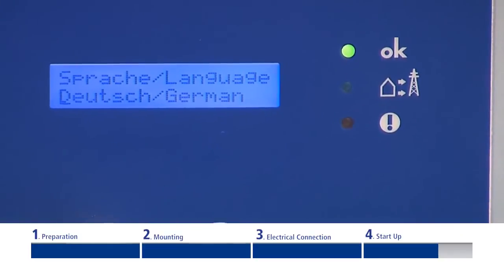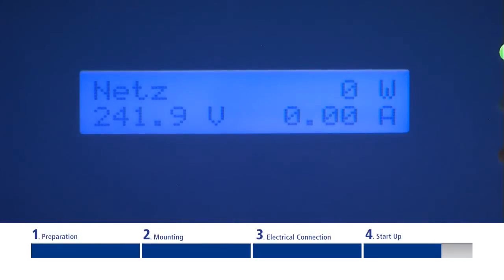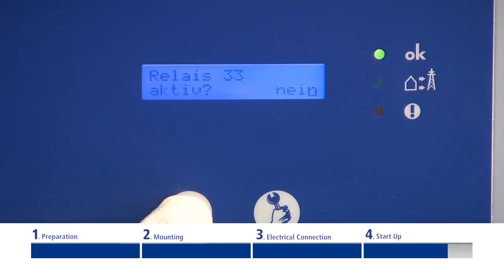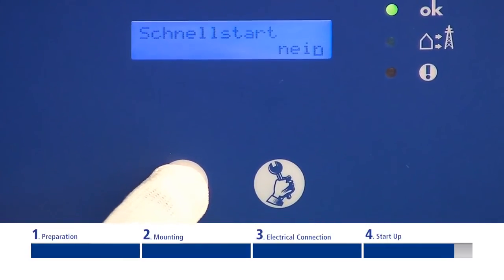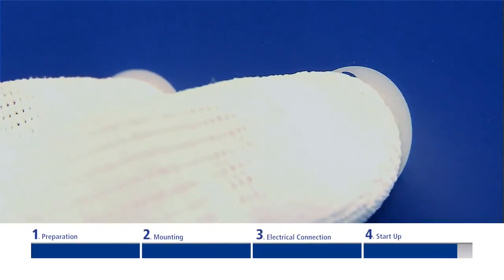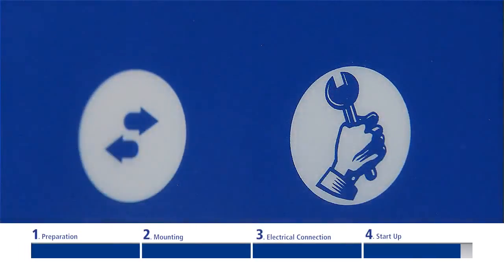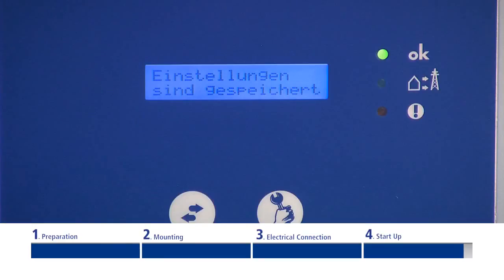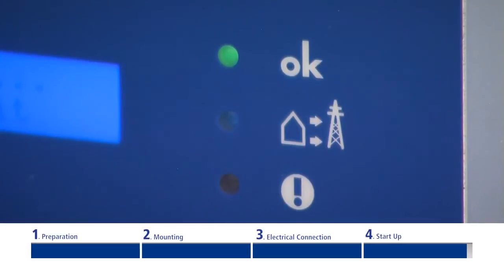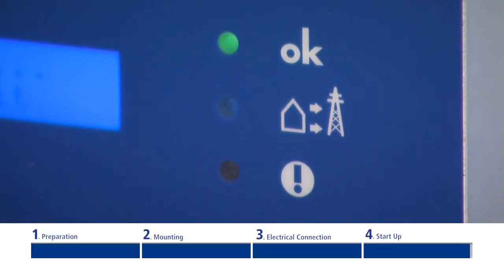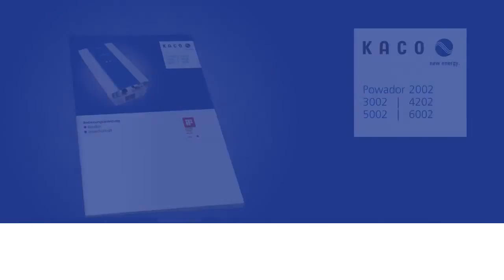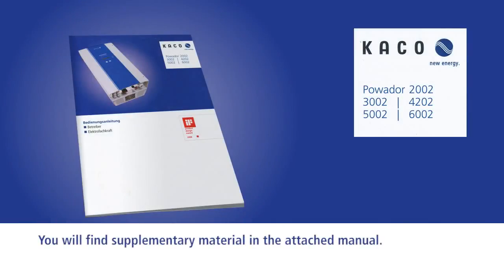The top LED diode lights up when in non-grid feed mode and indicates that it is ready to be put into operation. The display now indicates the current generator voltage. Optionally, you can carry out a quick start. You will find more details in the installation manual. To leave the parameter menu, press both buttons at once. The settings will be saved. Congratulations, you have now successfully completed the installation, and the inverter can now be put into operation. You will find extra explanatory material in the inverter's comprehensive operational instruction guide.